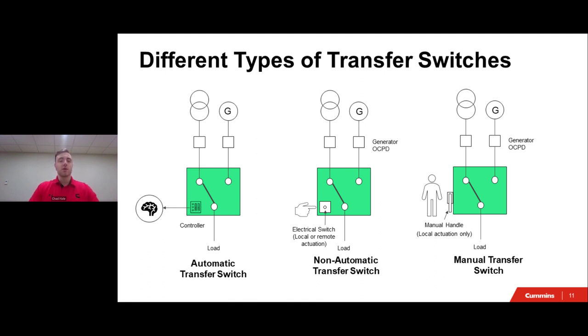Consequently, this means that they work best in applications where transfers between two live sources are unlikely or unnecessary, or systems can tolerate differences in electrical characteristics of power sources and load circuits. Other considerations include that the manual transfer switch must be located where it can be accessed easily and that it cannot be controlled from a remote location.